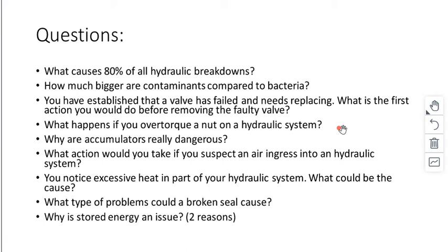What type of problems could a broken seal cause? Okay, so first of all, it could generate seepage, yeah. So oil leaks out. So we would have a pressure loss. So that's one thing. And then obviously there's a health and safety aspect as well, that it could cause injection injury. We're losing oil. It's got to be contamination of the environment and so on. The biggest issue is that the hydraulic system is not going to last very long. So if a seal is broken, we need to change it as fast as possible.